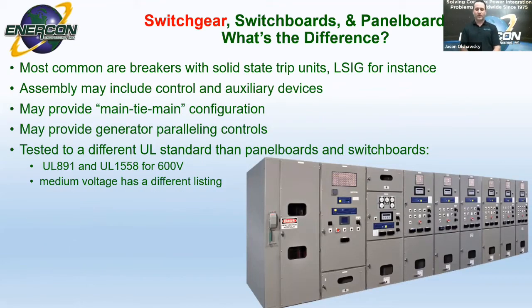So most commonly, switchgear breakers are equipped with solid state trip units. For example, you may see a spec requiring LSIG breakers. These letters signify the type of protection and available adjustments on that circuit breaker. So the L stands for long time, and that's what you would use for overcurrent or overload protection with a long time set point. S is for short time. So that would be some sort of a short or short circuit fault. I would be instantaneous, so that's a high level fault, and that's going to be your shortest time frame. And then you also have a ground fault protection there with the G.